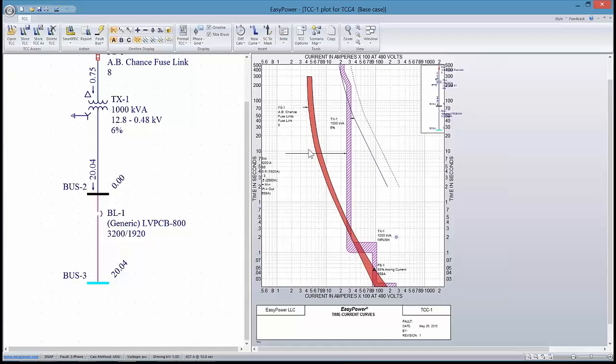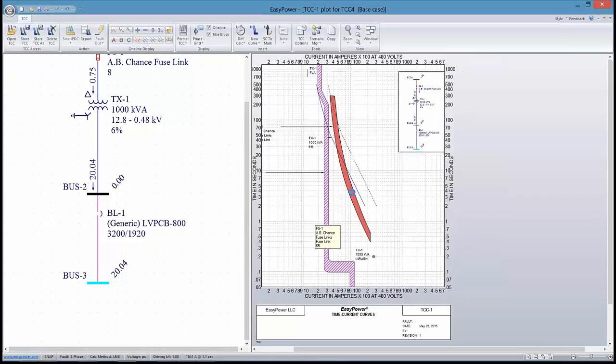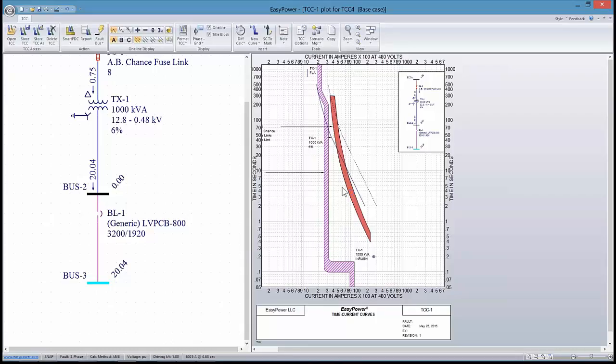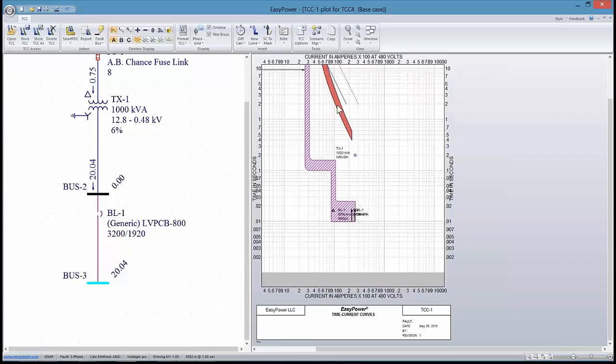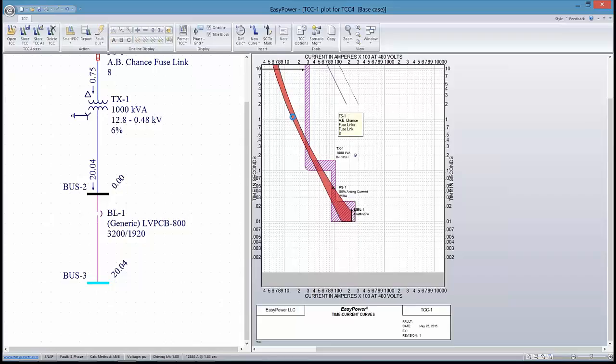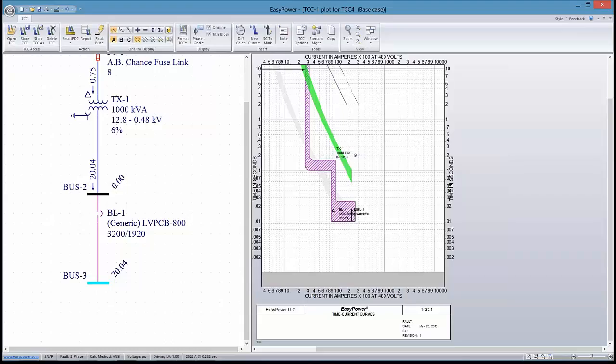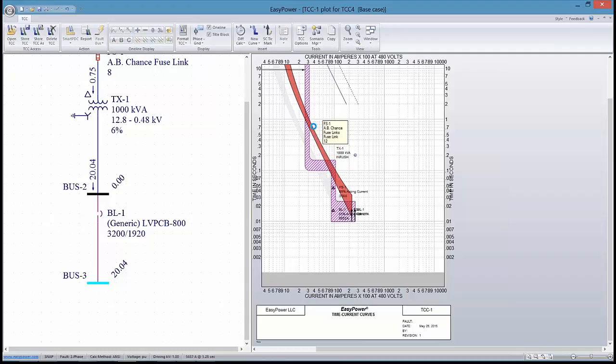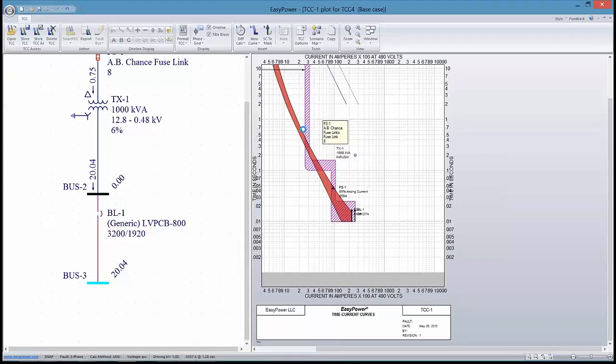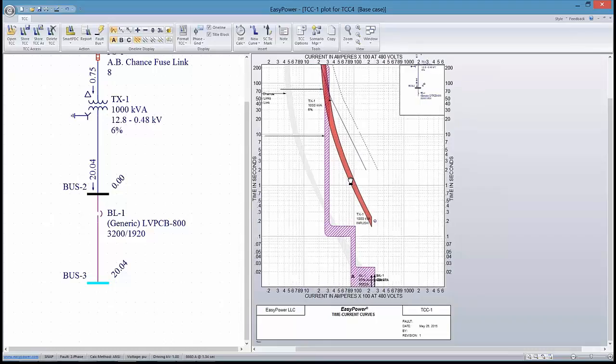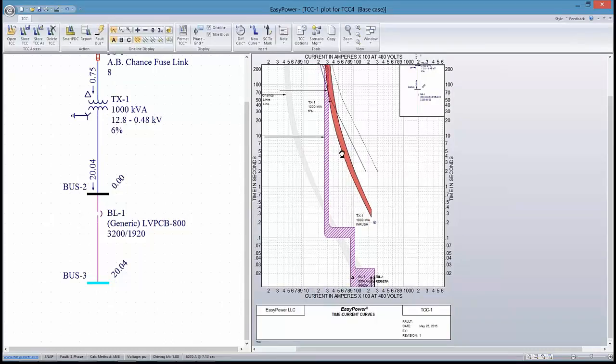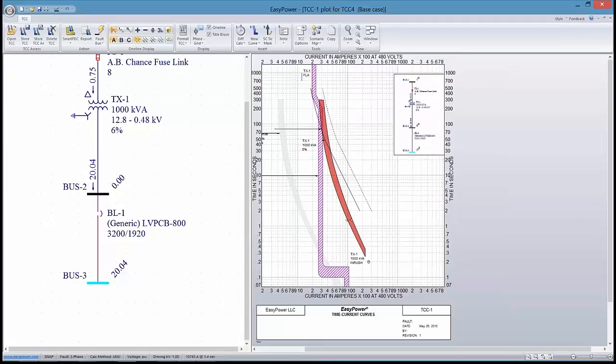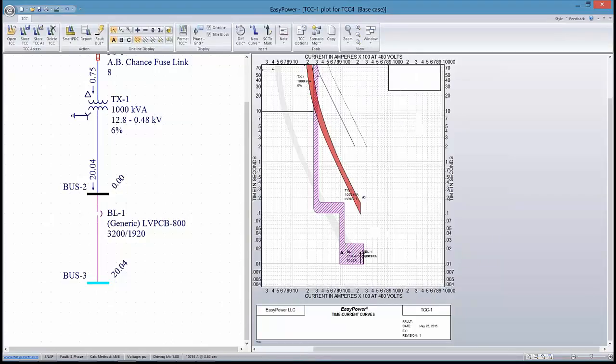In terms of how to mitigate this, clearly the fuse is going to have to be changed. The tool allows us to approximate what a better selection of fuse might be. I don't want it to be the primary protective element, so I'm physically dragging it. If I right click and show the original curve, you can see that this is where we started off. As I pull it up out of the way, I'm not making an adjustment on the fuse. What I'm actually locating is other values in the particular family and type of fuse. If I picked a fuse of size 30, then the performance overlap would be as we're showing here.